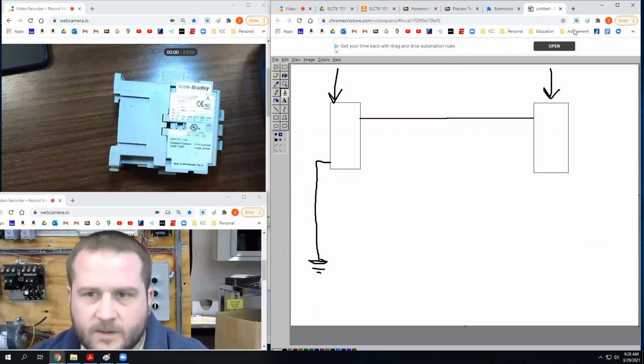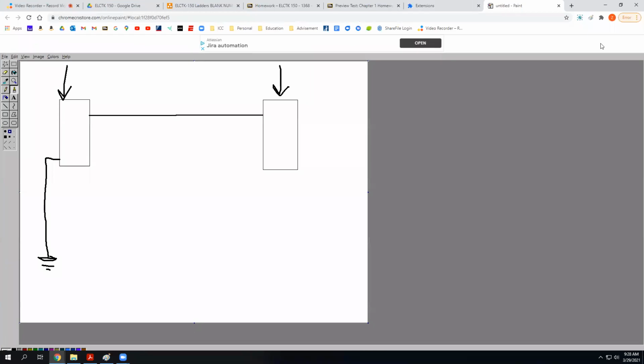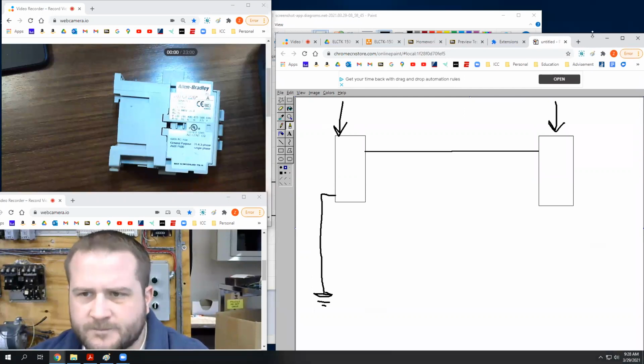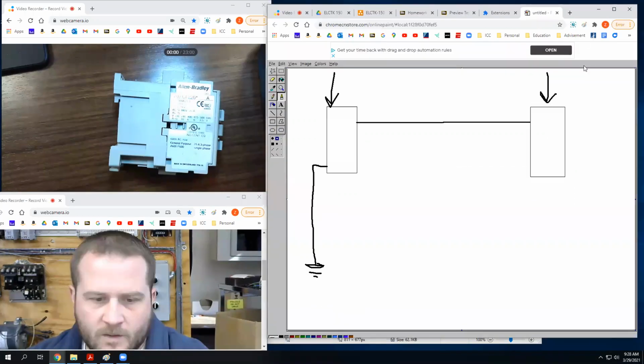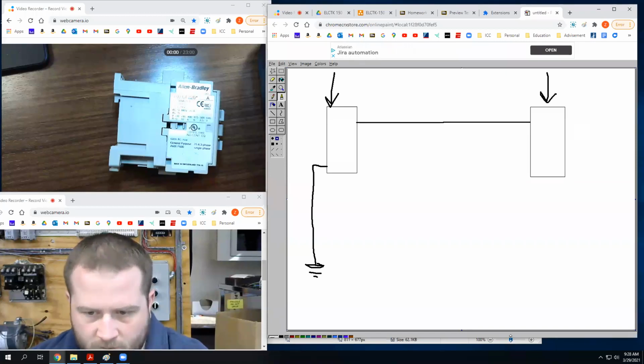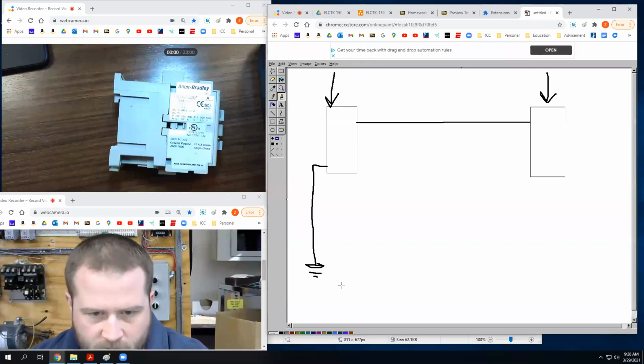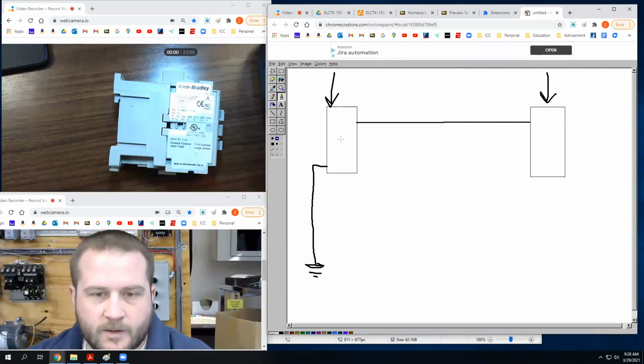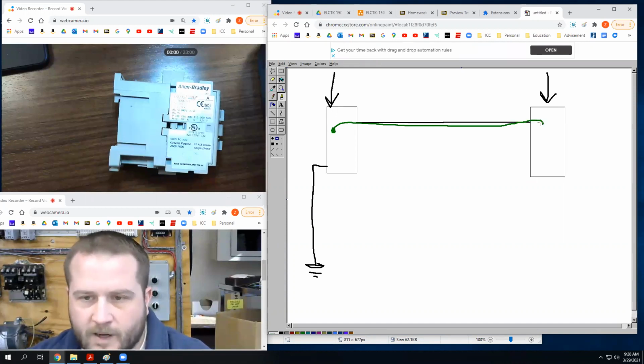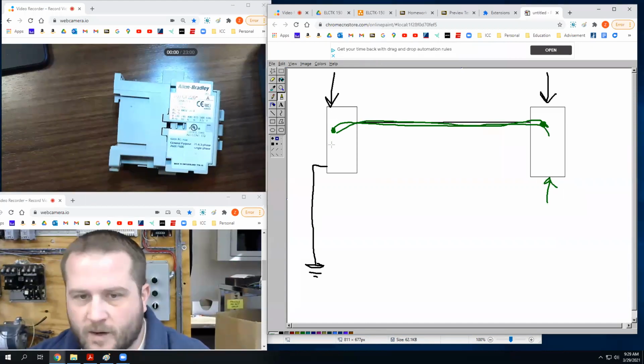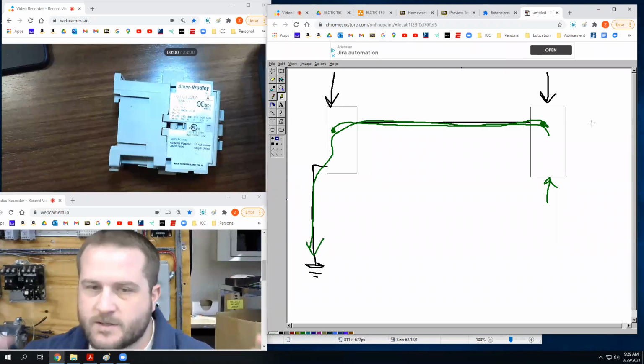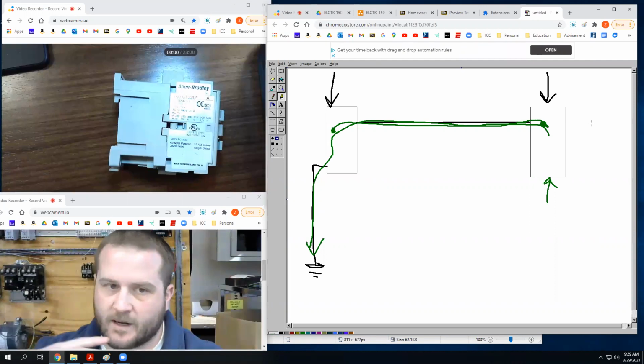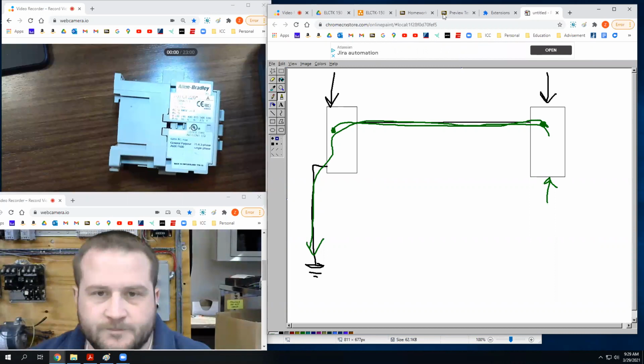So if this is a PVC conduit - let me get my colors here, sort of green - from this point there's going to be a way to put a little green screw in here. If I run that wire through the conduit and make it up in here, then I'm bonding those two pieces together. Now this one is grounded too, through this green wire into earth ground. So that's the difference: bonding just means bringing two pieces of equipment together and making them electrically continuous somehow. Everybody got it?